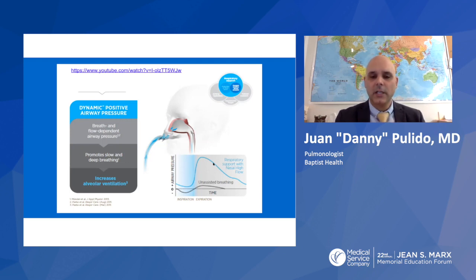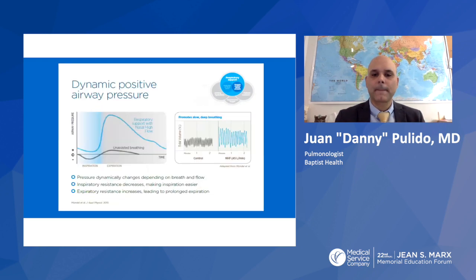So yes, in essence, if patients are very immobile, bedbound, or have neurological conditions that hamper their breathing capacity, you do have to worry about atelectasis as being a serious complication. One way to help prevent this is by adding positive expiratory pressure on their exhalation phase with this type of therapy.